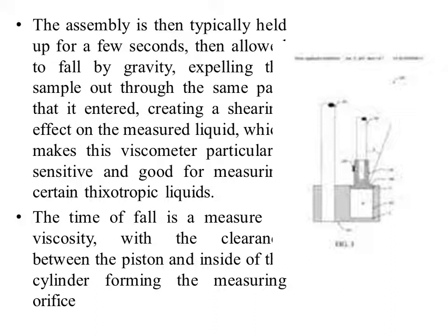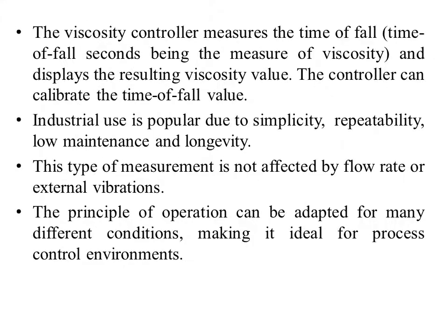The time of fall is a measure of viscosity, with the clearance between the piston and the inside of the cylinder forming the measuring orifice. So with the piston falling on the liquid, you will be measuring the viscosity. The viscosity controller measures the time of fall and displays the resulting viscosity value. The controller can be calibrated and the time of fall value can be measured.